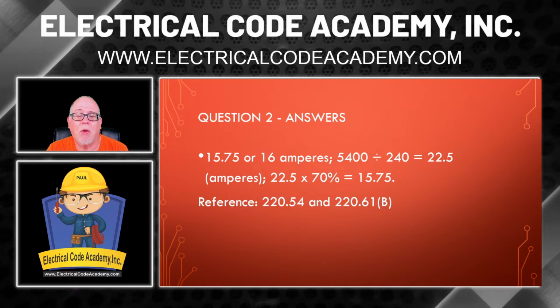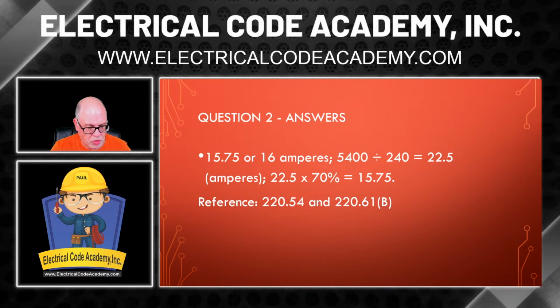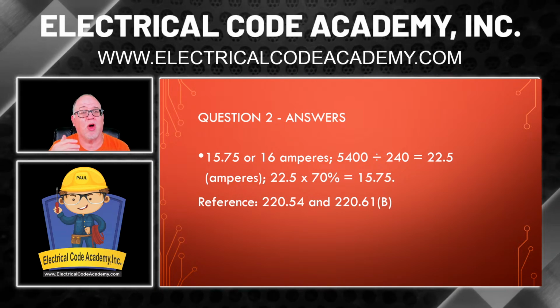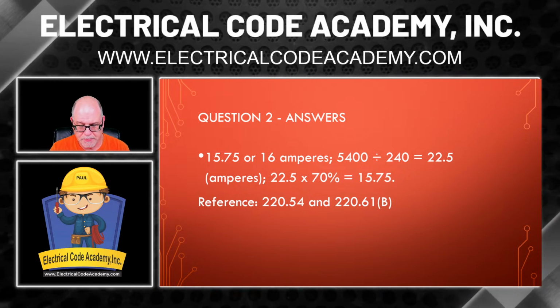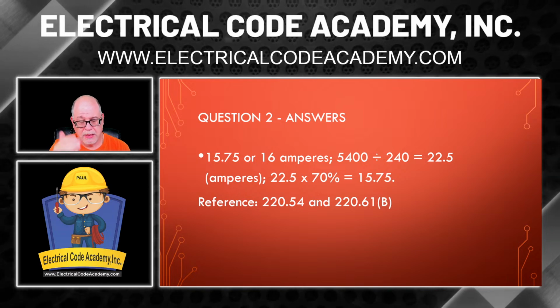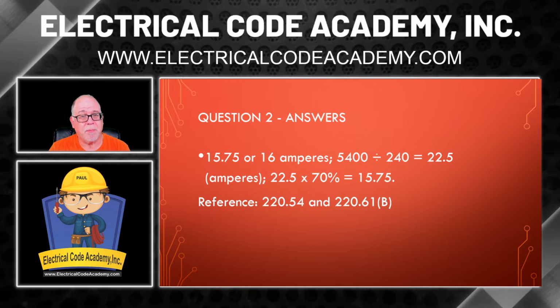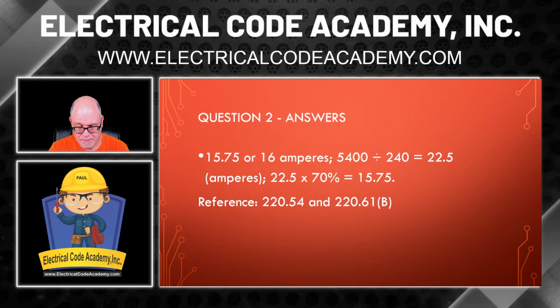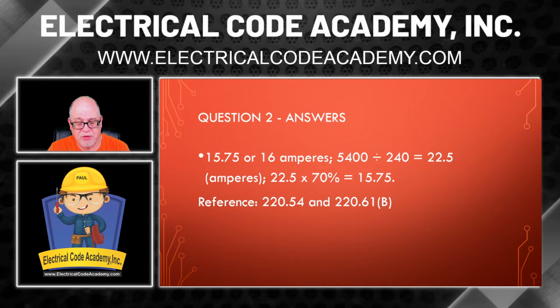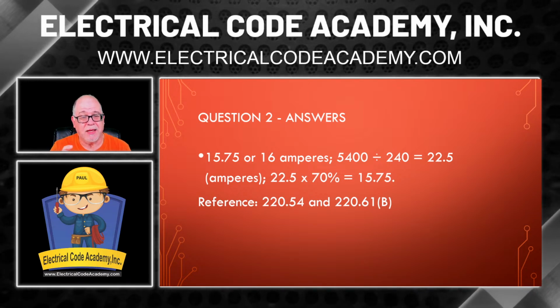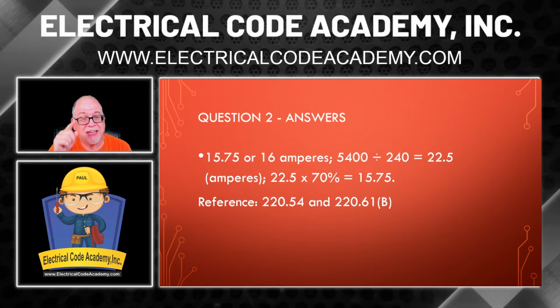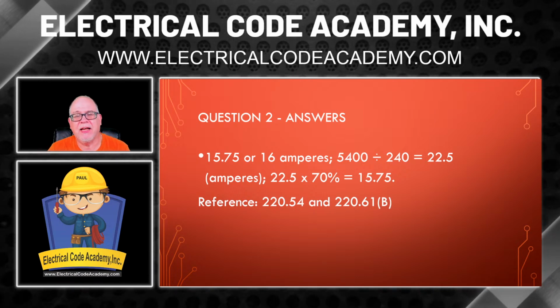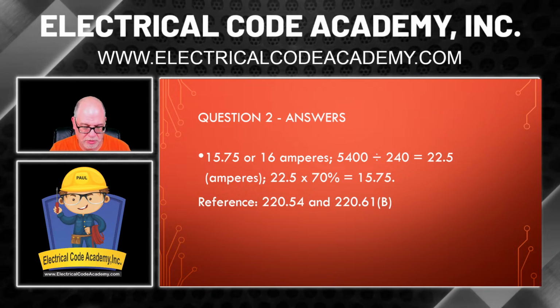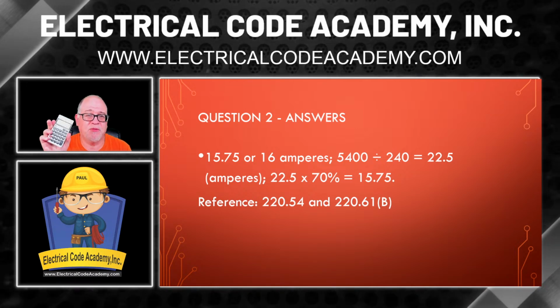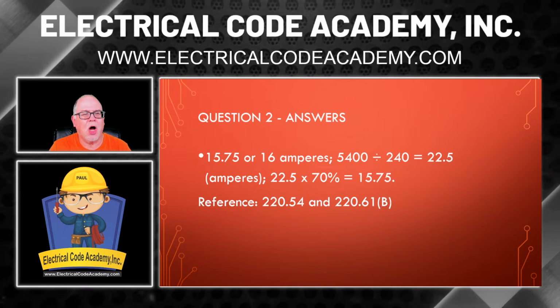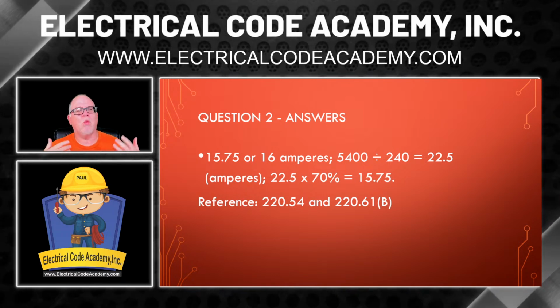Now, I want to talk about the other way you could have done this. One other way is to start with our full value, our 5,400, and you could have multiplied that by 70%. And that gives you 3,780 VA. Then you could take that and divide that by 240 volts. And that also gives you 15.75. Always remember, there are many ways that you can do this.